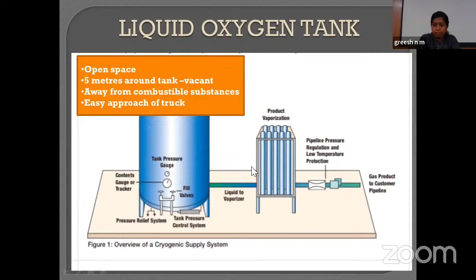The liquid oxygen so produced will travel to the vaporizers. From here, the gaseous oxygen will be generated. There are two types of vaporizers: a simple vaporizer and a duplex vaporizer. A duplex vaporizer has two sets of vaporizers, and when one is operating, the other gets defrosted. The gaseous oxygen so produced will either be collected into gaseous cylinders, or delivered to the patients directly by pipelines or via the manifold.